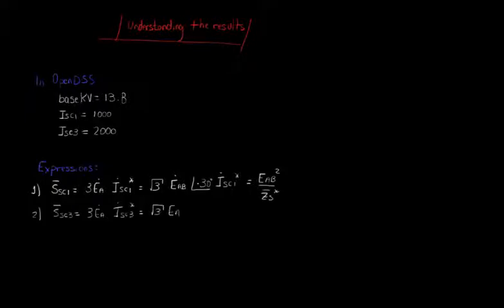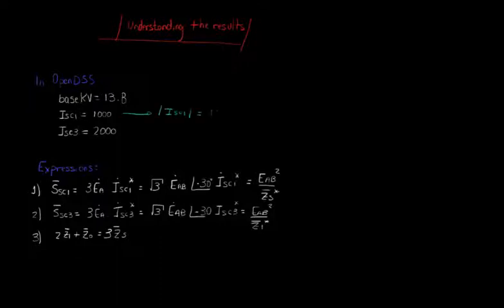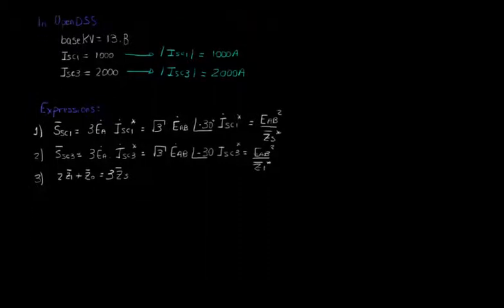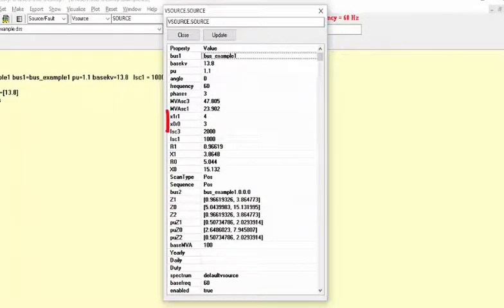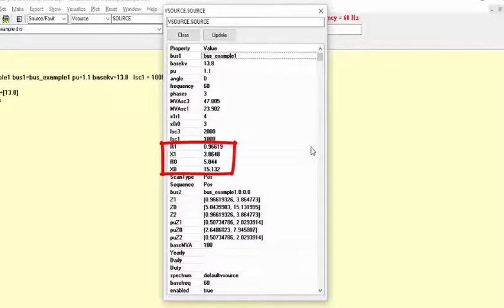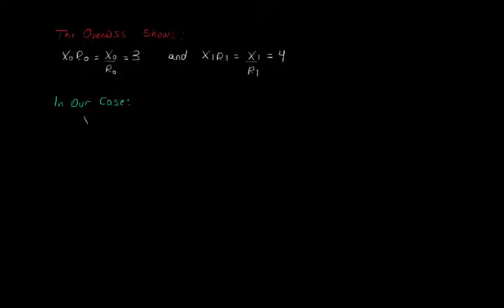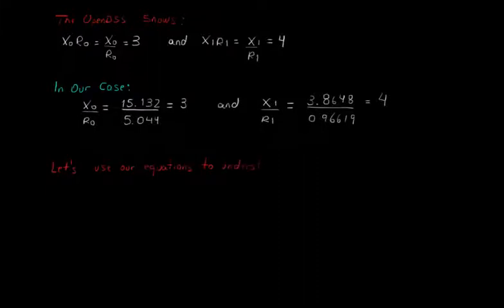The key point here is that when you define either ISC1, ISC3 or MVASC1, MVASC3, OpenDSS understands these parameters as a module. In our case, for example, it means that the module of ISC1 is equal to 1000 and the module of ISC3 is equal to 2000. If we pay attention to the table with the description of the vSource element, we can notice that there are two parameters called X1R1 and X0R0. They define the ratio between X1 and R1 and X0 and R0, and by default their values are 4 and 3, respectively. From the table, if we take X1 divided by R1 and X0 divided by R0, we will get exactly 4 and 3, which means that the OpenDSS default values of X1R1 and X0R0 are being used.